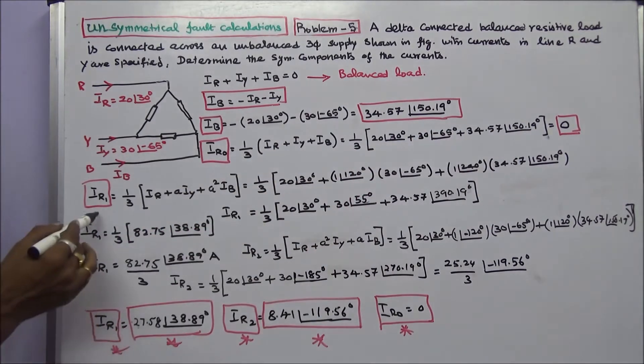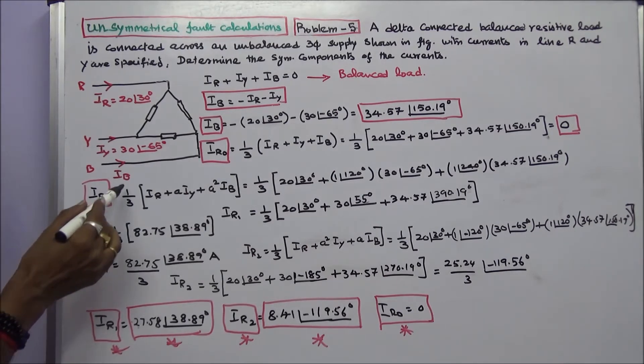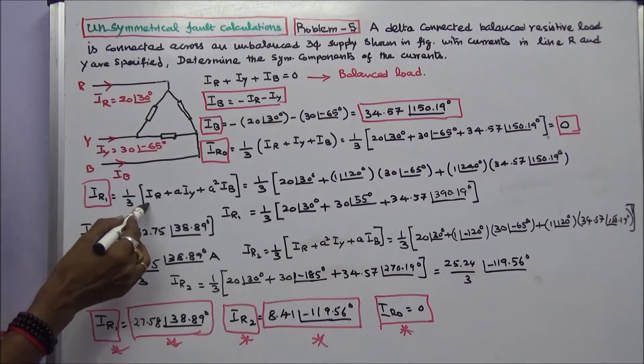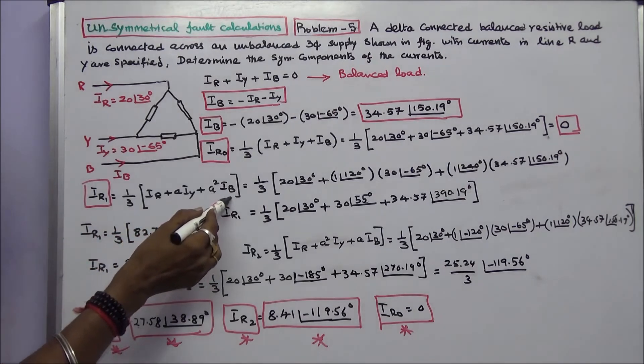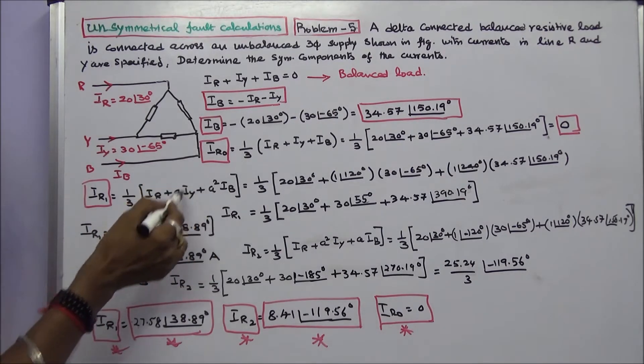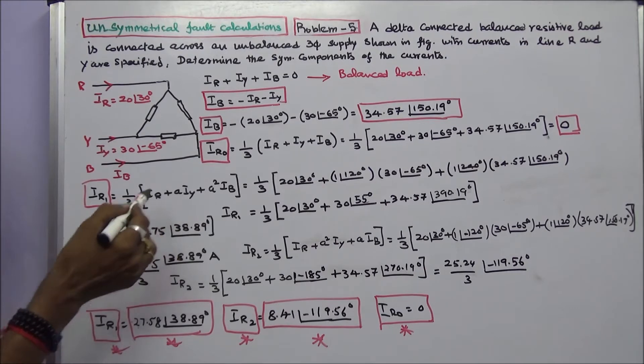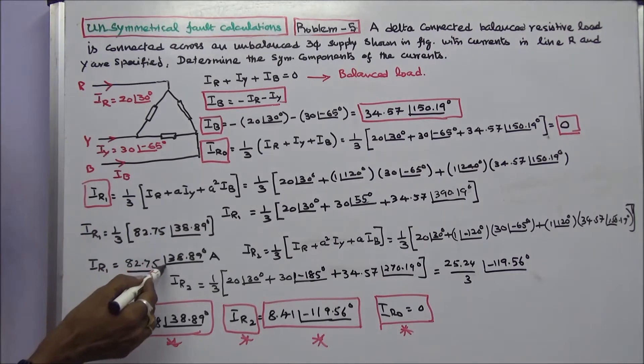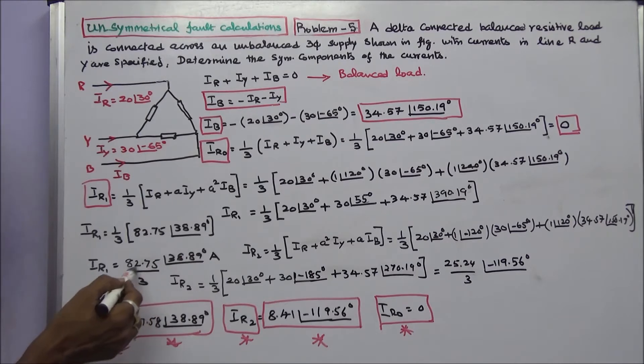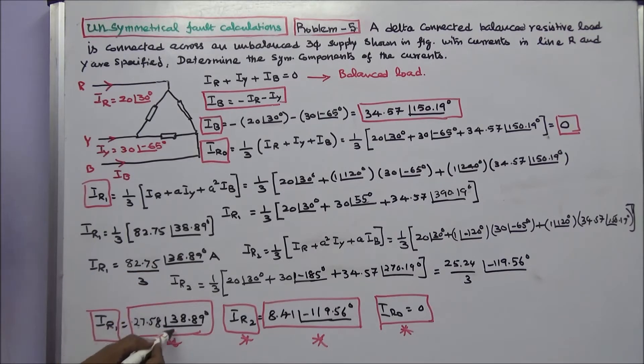Next we calculate IR1, the positive sequence current in the R phase. IR1 is equal to 1/3 into IR plus A·IY plus A²·IB. Substituting all the values, IR1 is equal to 82.75 angle 38.89 degrees divided by 3, which gives 27.58 angle 38.89 degrees.